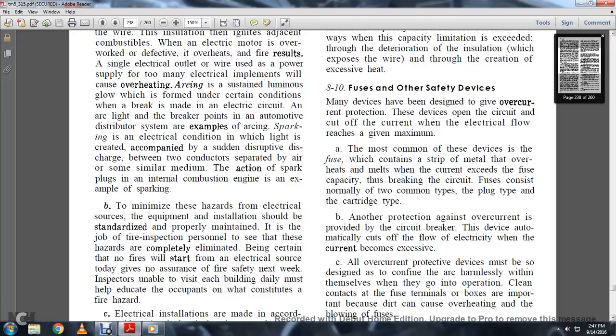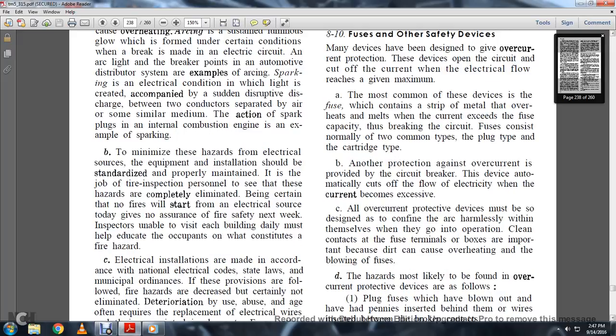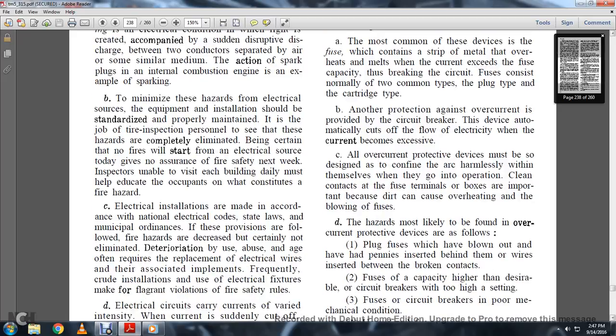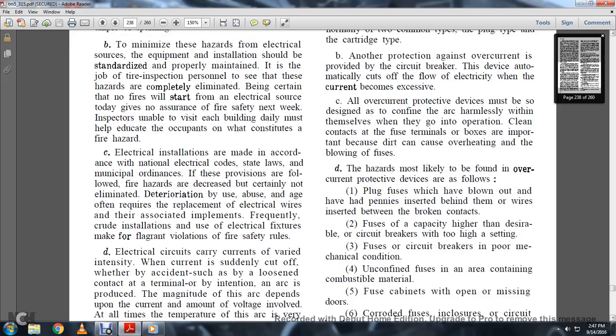The fuses normally consist of two common types, the plug type and the cartridge type. Another protection against overcurrent is provided with the circuit breaker. The device automatically cuts off the flow of electricity when the current becomes excessive. All overcurrent protective devices must be designed to be harmless within themselves when they go into operation.